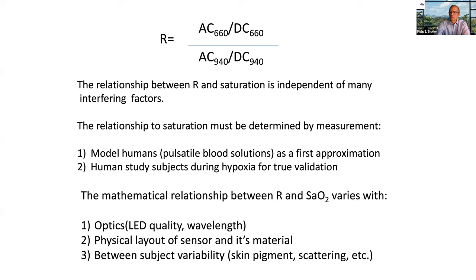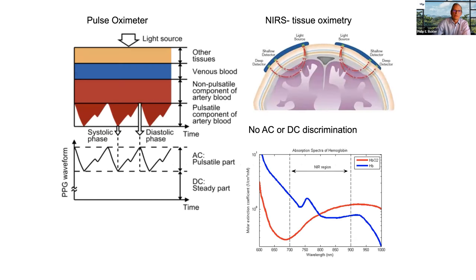And there are various tricks of the trade that come into play to build a pulse oximeter. You need good optics, good light-emitting diodes to produce a pure wavelength of light. The performance is dependent on the type of material that's used in the sensor, and there's a wide variety of things that come into the engineering. But the basic concept that Aoyagi envisioned 50 years ago is still in use today. So the graphic on the left shows this concept in a different form.